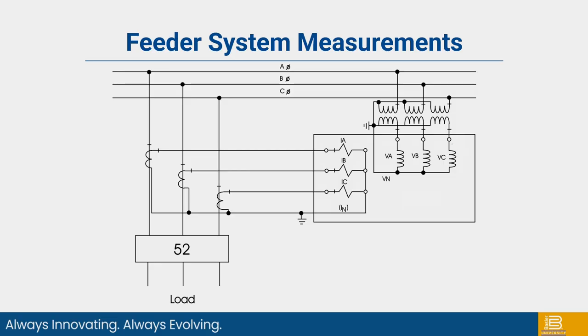Here's a typical feeder system showing a 3-line diagram and how you would connect it into the BE1-FLEX. On the bus side of the feeder breaker, there are the PTs, which are a 4-wire Y connection into the BE1-FLEX, along with the 3-phase CTs for each phase, A, B, and C. And notice the polarity marks and how they're situated on the relay.